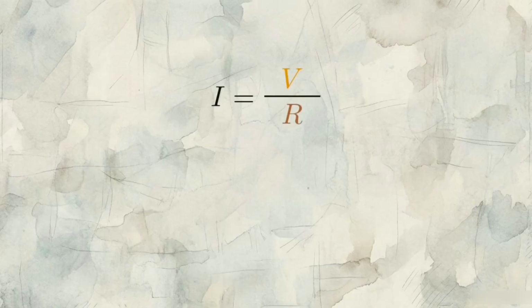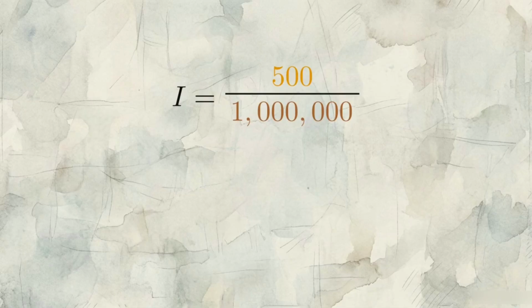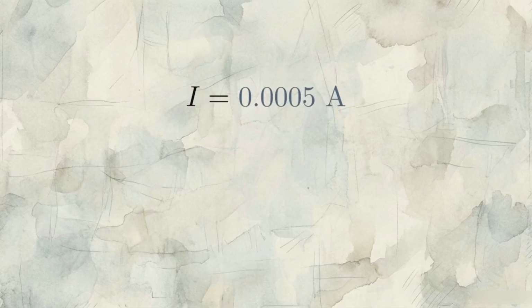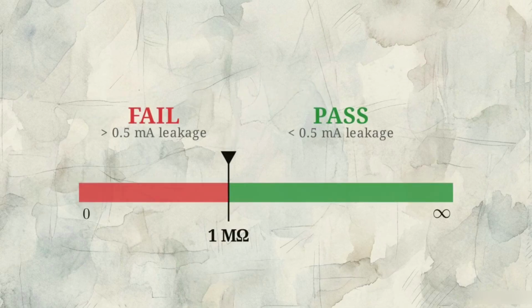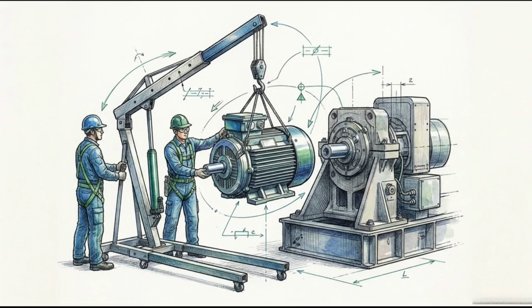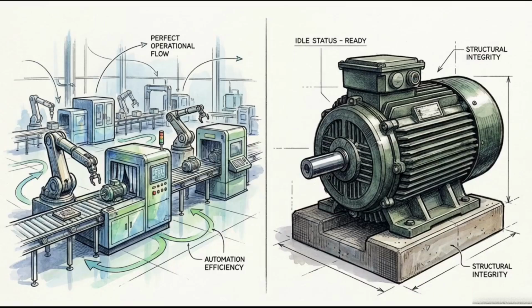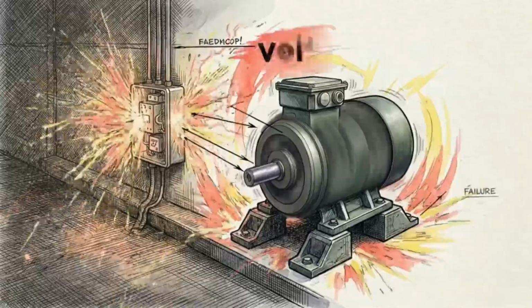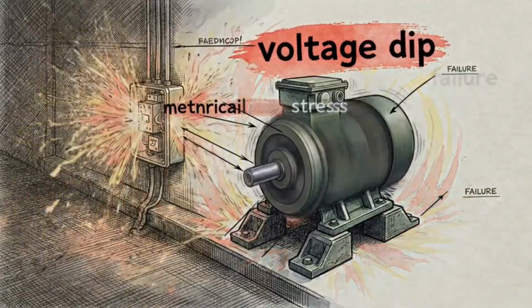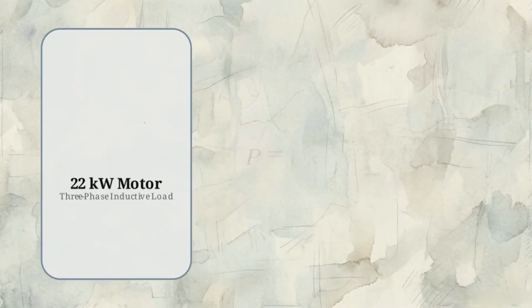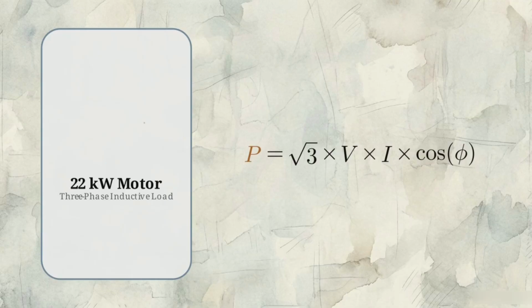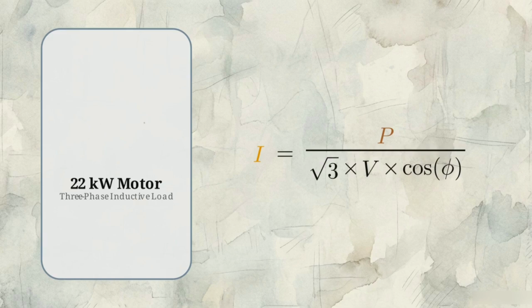With our 500-volt source, we look for a resistance of at least 1 million ohms, or 1 megaohm. At exactly 1 megaohm, the leakage current is 0.0005 amps, half a milliamp. Any measurement below this threshold indicates failing insulation. Measuring this microscopic 0.5 milliamp leak is the difference between a controlled, scheduled motor replacement and an explosive, entirely unscheduled factory shutdown. Even when components are healthy, the physics of starting a machine can destabilize the entire plant. When a 22 kilowatt motor is started abruptly, it can cause a voltage dip severe enough to dim the facility and trip every adjacent machine.